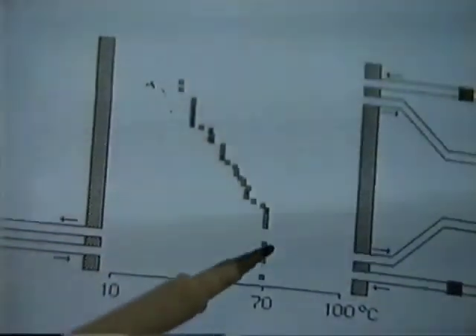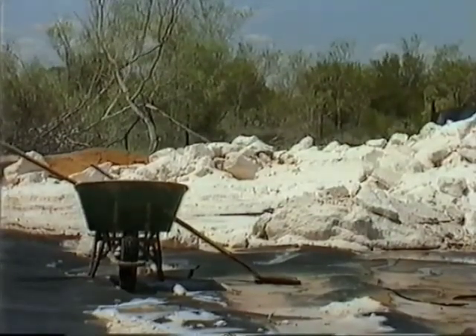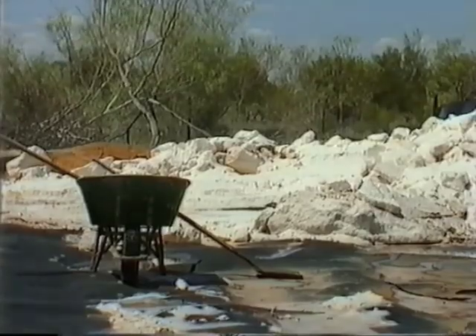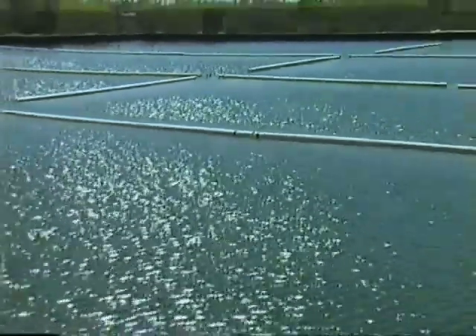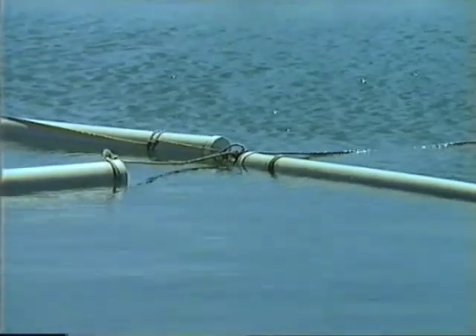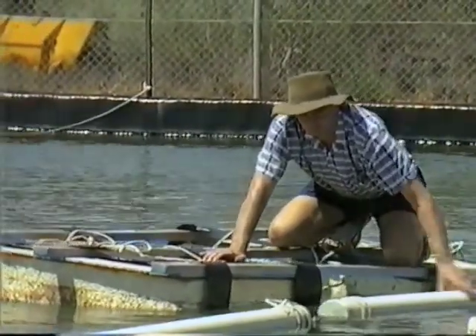In this graph, you can see the temperature as you go down to the base of the pond, where it's almost 80 degrees. The salt for the solar pond is actually produced right next to the pond by allowing heat energy from the sun to evaporate salty water from beneath the earth's surface. The solar pond requires care and attention to keep it working efficiently. PVC plastic pipes floating on the surface stop waves developing and so prevent salty layers from mixing. The alignment of these floating pipes must be checked regularly.